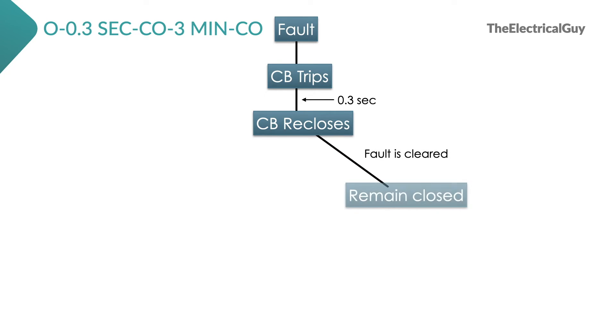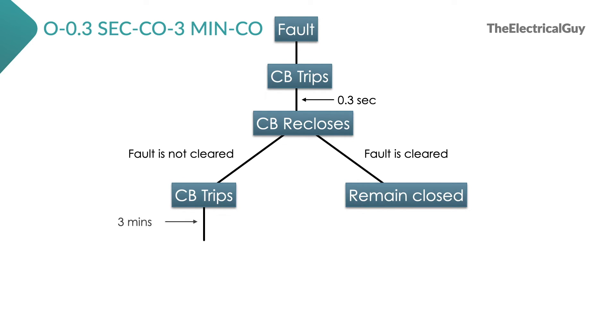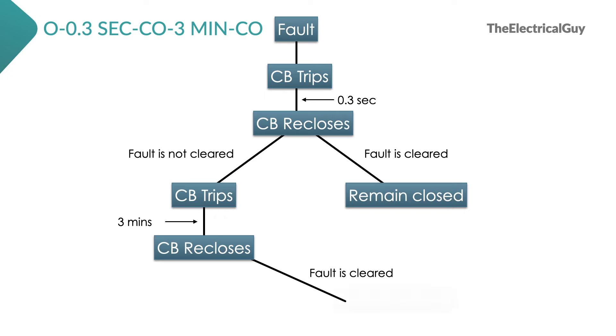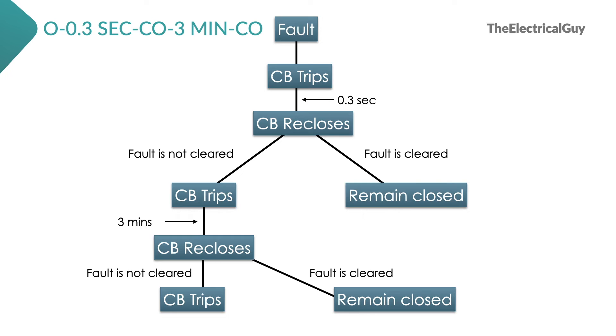Let's say there is a fault on the system and the breaker opens. It will remain in open condition for 0.3 seconds. After 0.3 seconds, it will close again automatically — if the fault is cleared, it will remain in closed condition. But if the fault is still there, the breaker will open immediately. Now the breaker will remain open for 3 minutes. After 3 minutes, the breaker will close again — if the fault is cleared, it will stay closed. But if the fault is still present, the breaker will open immediately again and remain in open condition until it is closed manually. This is one of the very important features of a circuit breaker.